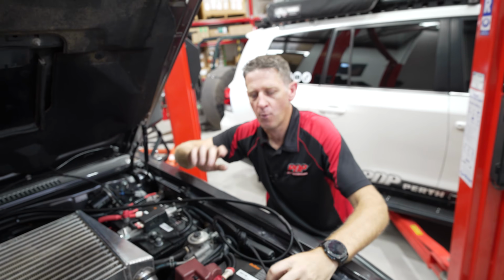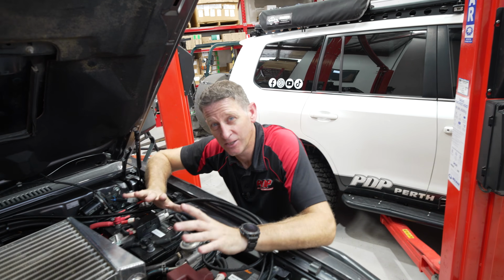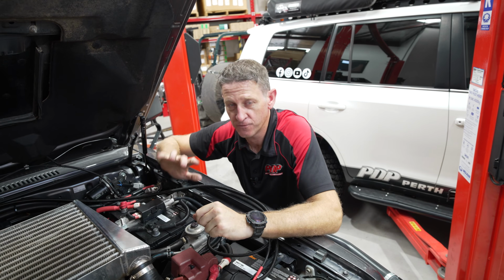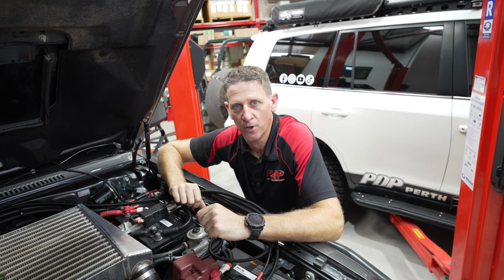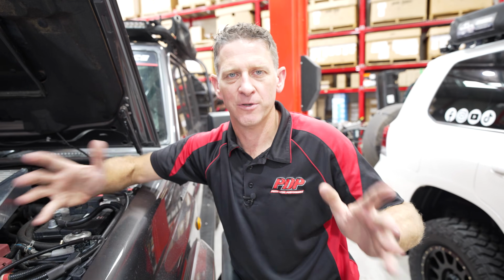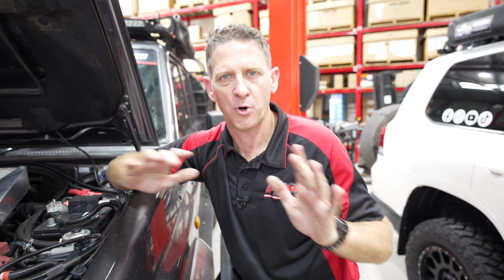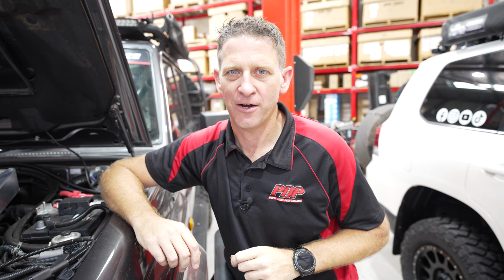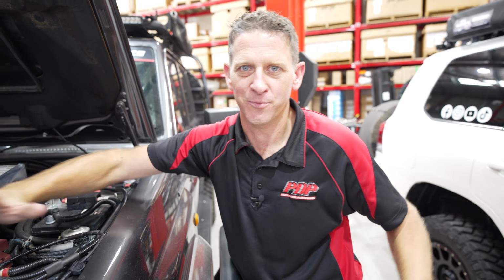They are fusing the fans individually. Now also, I may mention, we do have an auxiliary pickup that you can override the fans from the controller, that's in the loom as well. And just like that, all the wiring's done. Now it's time to verify the fan, the direction, and program it. Disclaimer, I'm going to show you that on the 200 because the fans are on my vehicle.